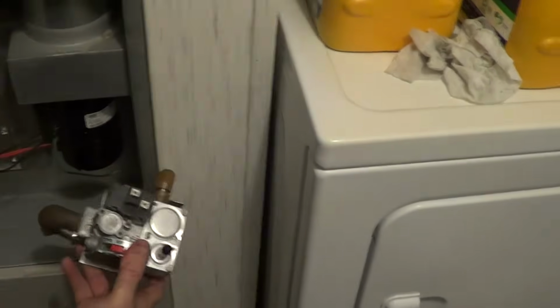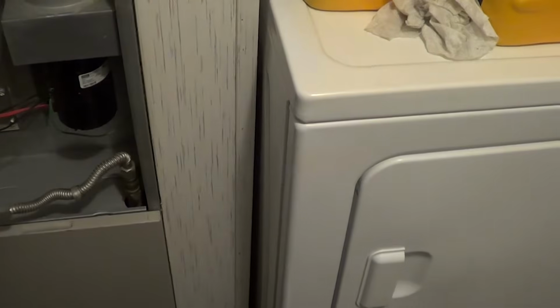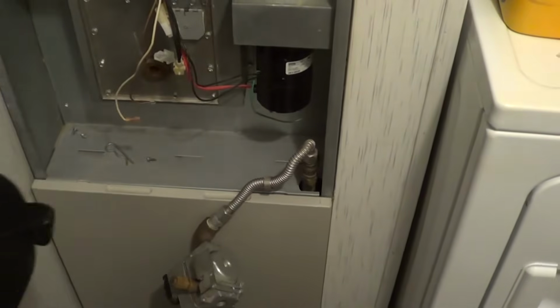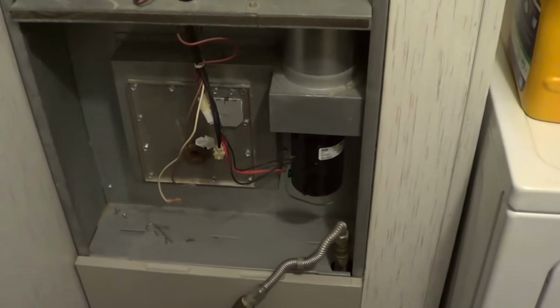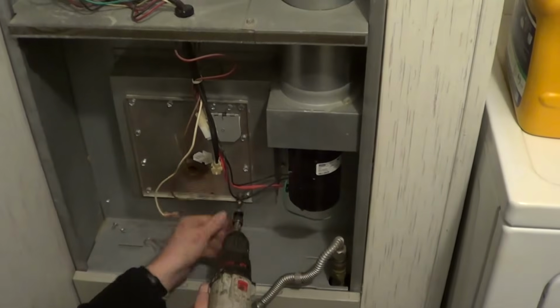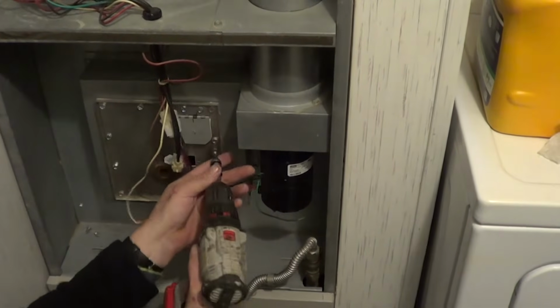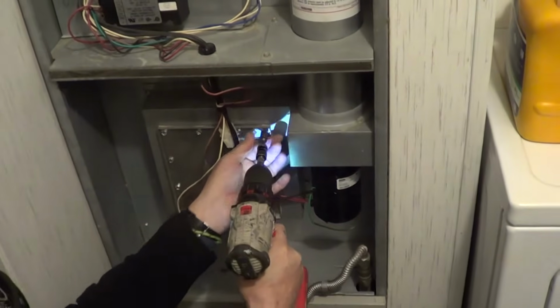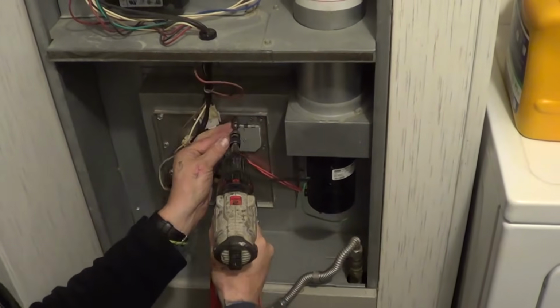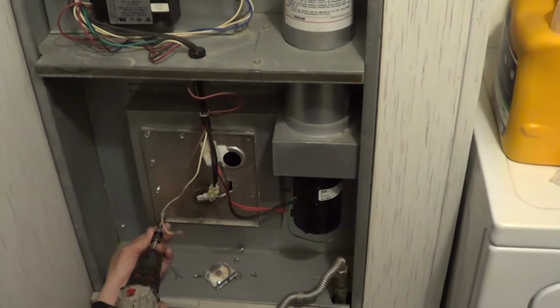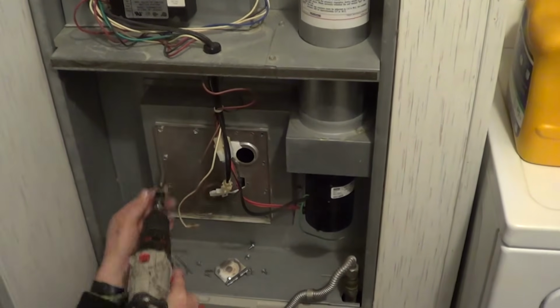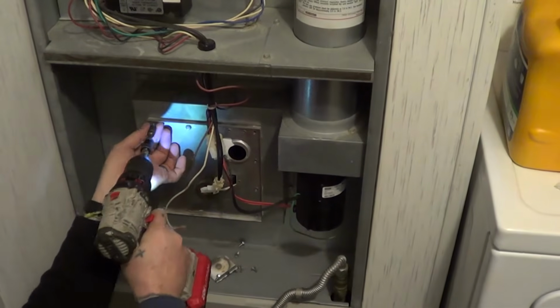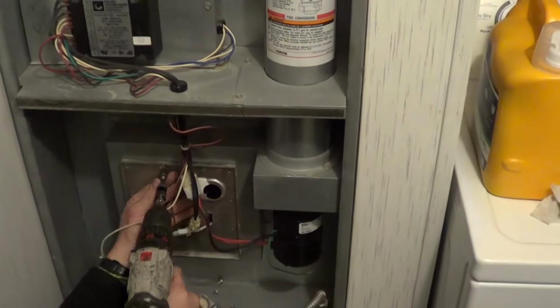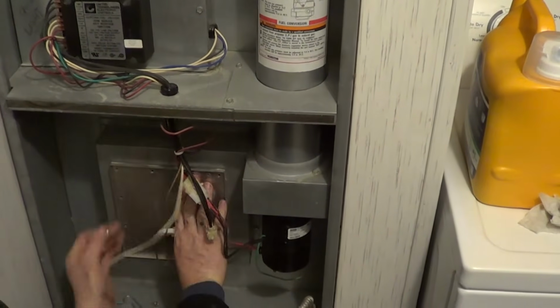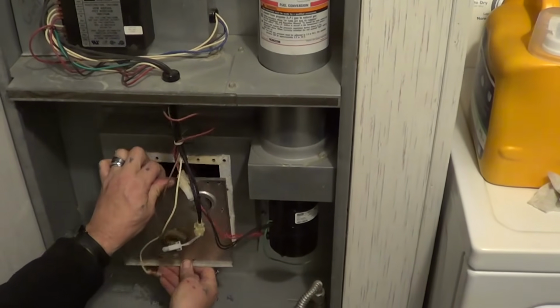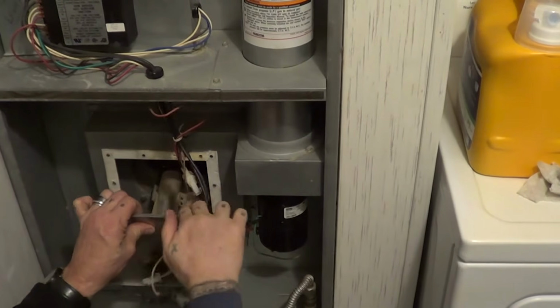So if we were going to replace this valve, of course, now we just take the connectors off, reuse this, put it all back together, and do the opposite of that. But we're going to look inside and check that heat exchanger while we're at it. So now we're going to switch to a 5/16, and we're going to take all of these screws off here. Okay, and here's the last one there. We're going to hold with our hand here, with some pressure so it doesn't fall down. When we take it out, we're going to give it a little pull and tip that end up a little bit and let it come straight out.